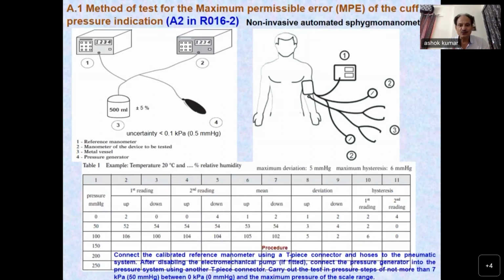Let me say a few words about our R16.1 and R16.2. What is the normal protocol? If you want to test non-invasive automated blood pressure devices, you have two sphygmomanometer observers in the line, then the device also in the line, and then a reference pressure point, which is calibrated with SI traceability. Whatever you generate, there are various parameters and environmental conditions you have to follow, more than 20.